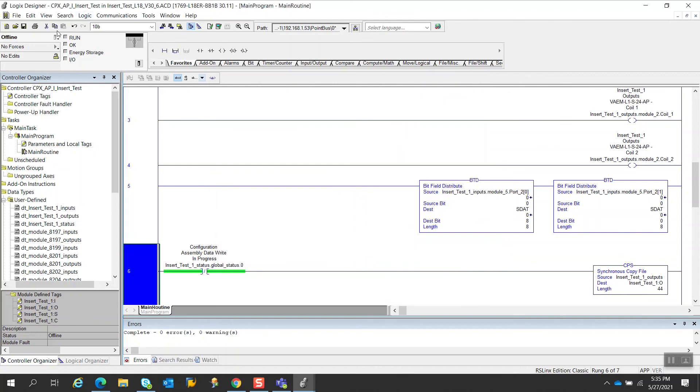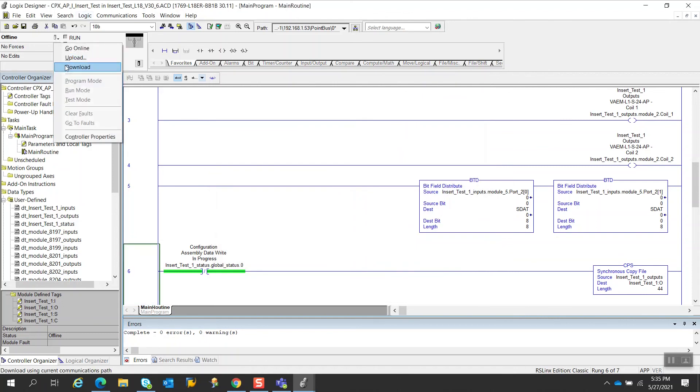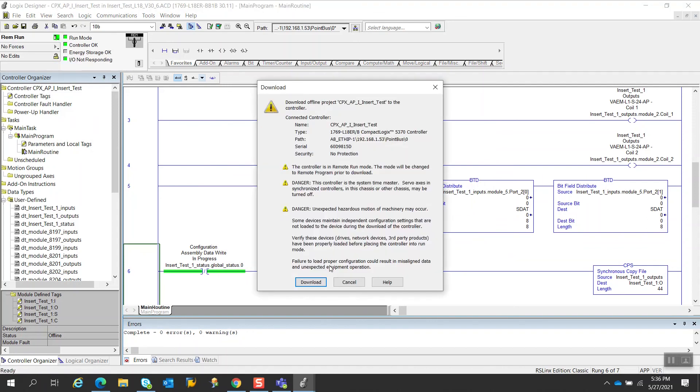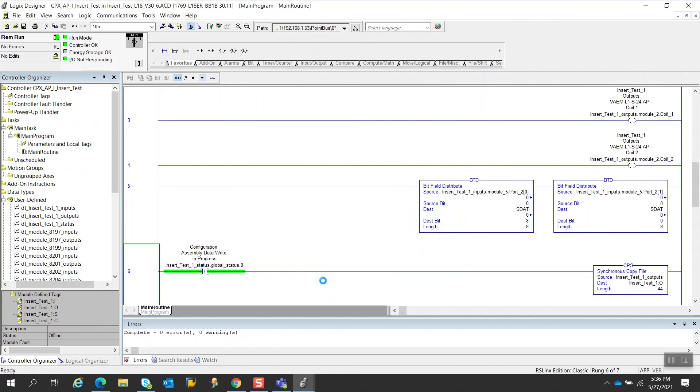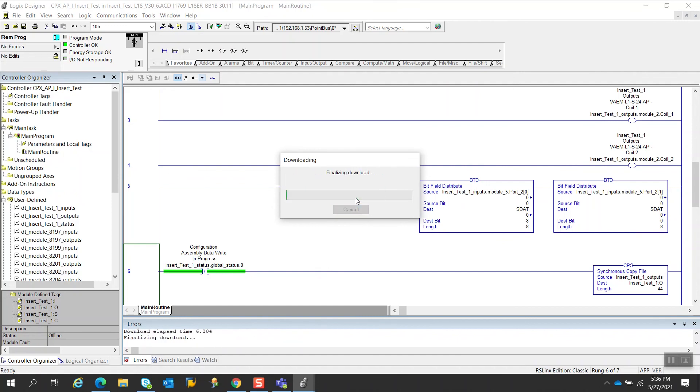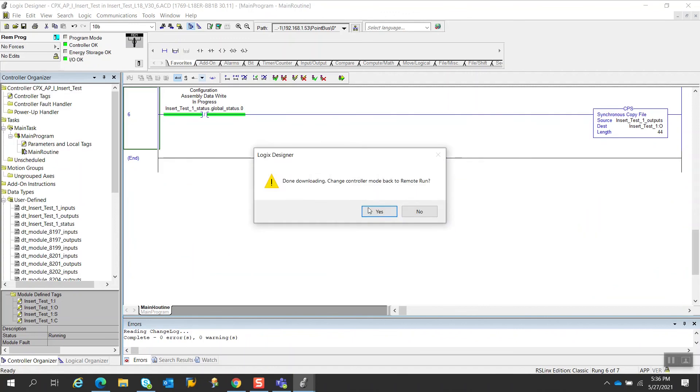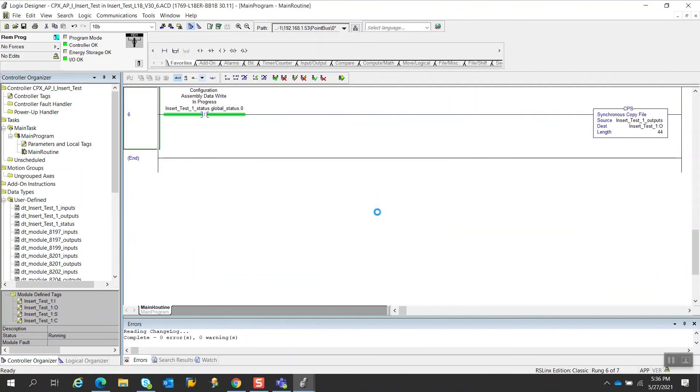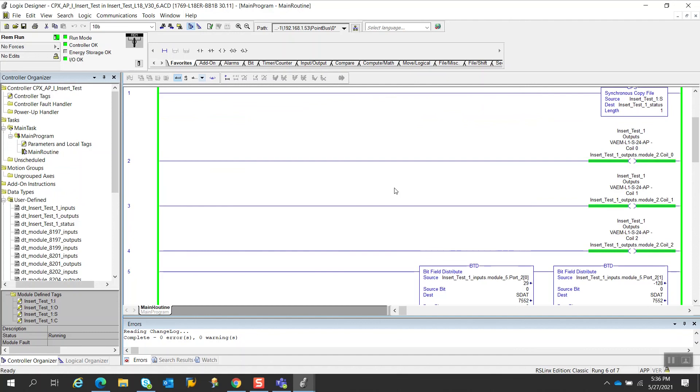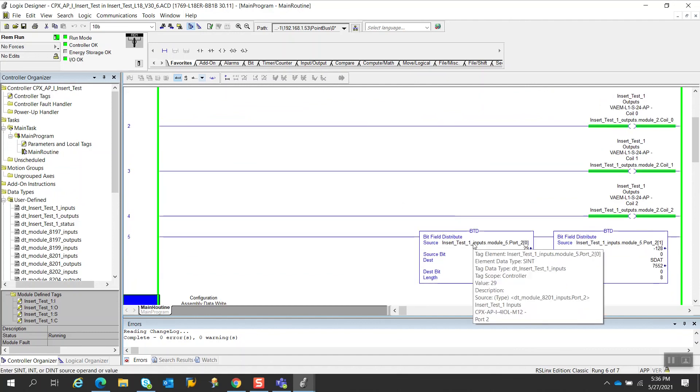Now I'm going to download this project to the controller. And then we go back into run mode. So I heard the valve click on. You see my CPX-AP-I is running. All these valves are on. If I look at my SDAT, the data is changing. So that is working.